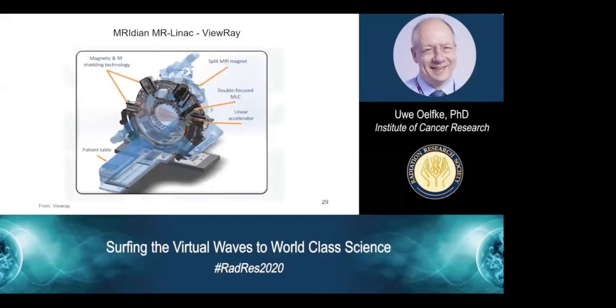In this slide, I show you then the next upgrade of the cobalt machine, where actually a linear accelerator was integrated into this technology. The split magnet still is the same, but you see here is the linear accelerator. There's a double focused MLC. I will talk about this data a little bit later. And then there are various components belonging to the operation of the LINAC, which are shielded in these buckets. They are mounted on a gantry, and now you have an operational LINAC on a gantry, which is positioned such that it's operating within a split magnet.